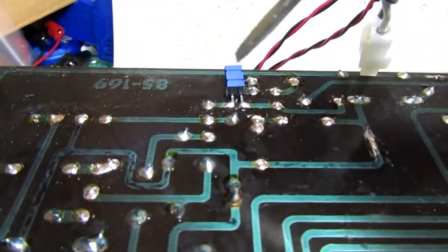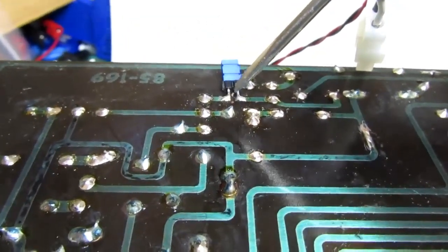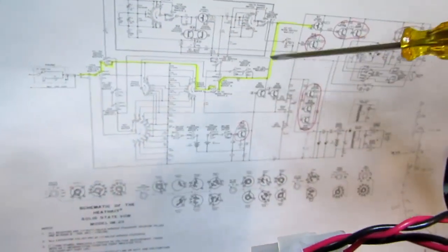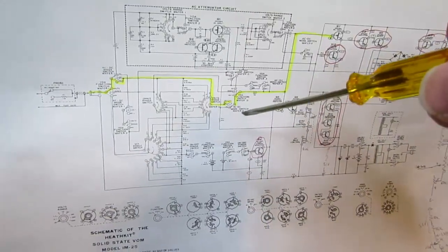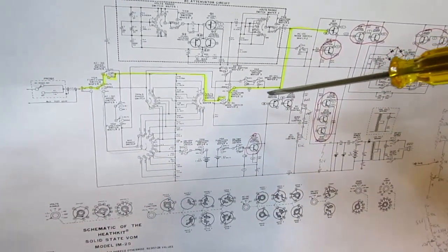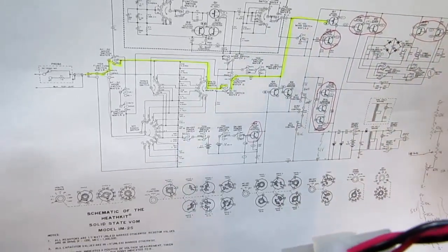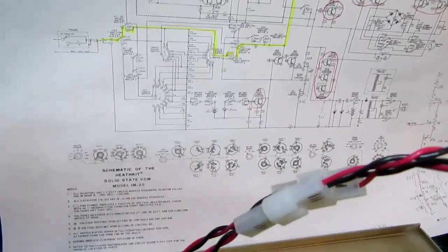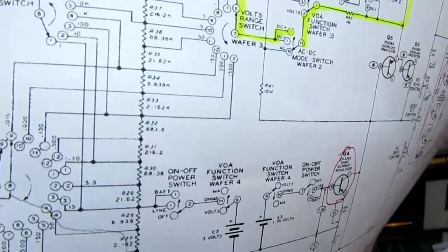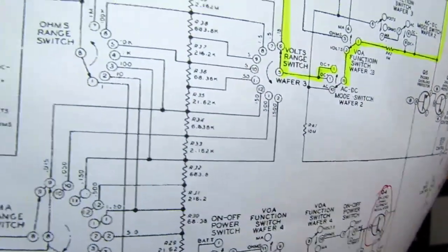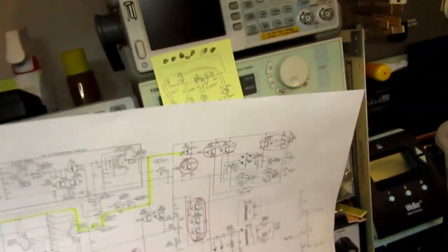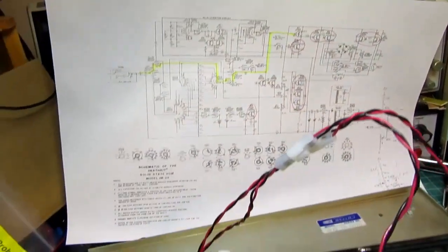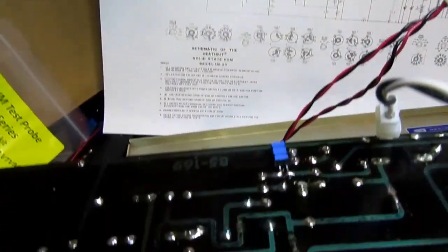And vice versa, like I said, by pulling the shunt off and measuring the voltage on the left side, you can see if all the front end circuit's doing its job, because no matter what range you're in, for a full scale reading it needs to have about, I think it's 0.15 volts on there. Well, it's probably not 0.15 volts, but it's a pretty small voltage. It's going to be what this circuit over here expects to see to give a full scale reading. It's a pretty small voltage. So you can measure that and do that.